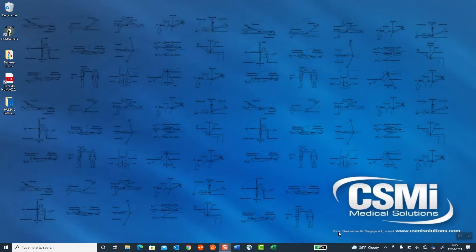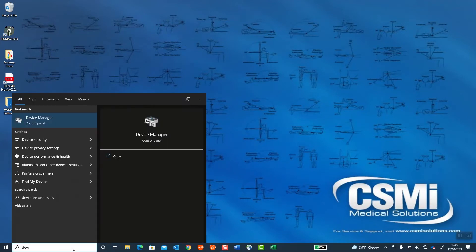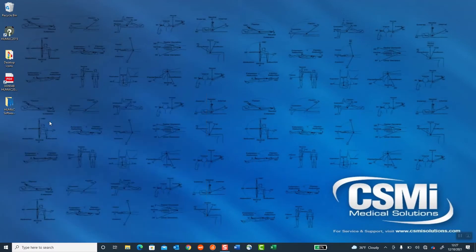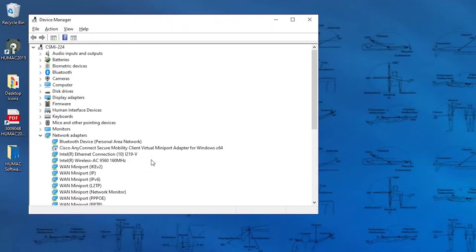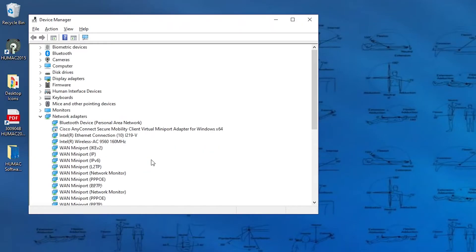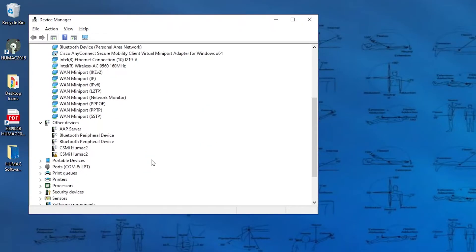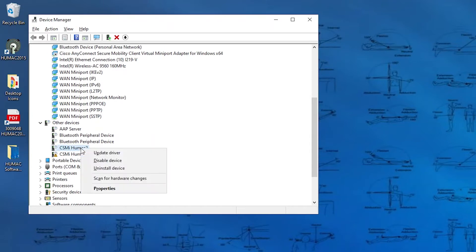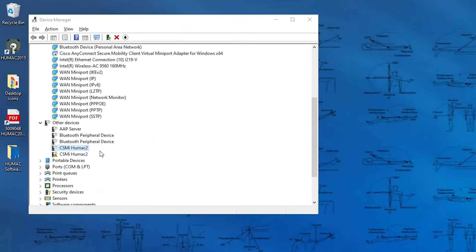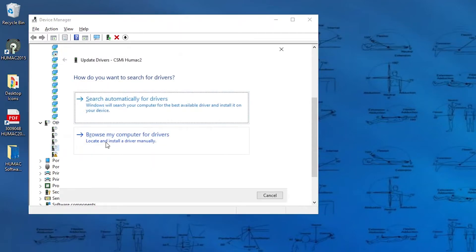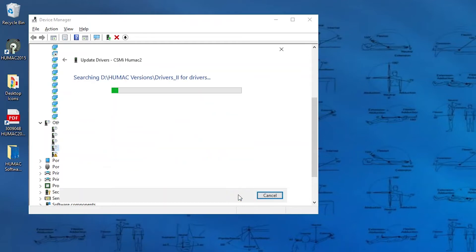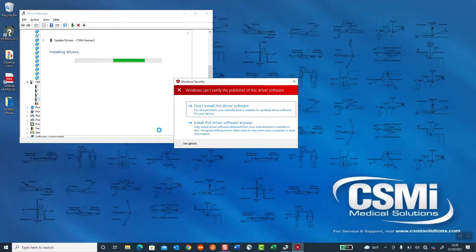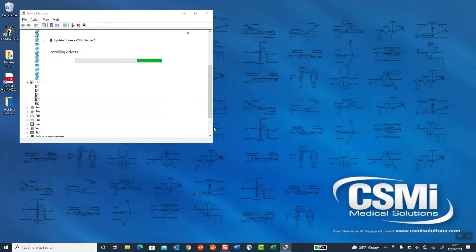Once your computer restarts, you want to go back to the Device Manager. You're going to look for the HUMAC under Other Devices. You're going to right-click on the first one. You're going to select Update Driver. Browse my computer. If it's not pointed to, point it to the Drivers 2 folder by using the Browse command. Select Next. Windows cannot verify the publisher of this driver software. Select Install this driver software anyway.